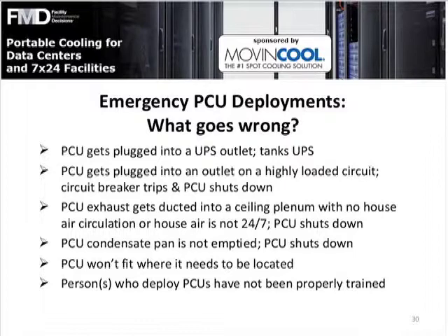Third example, exhaust gets ducted into the ceiling plenum with no house air circulation, or house air is not on 24/7. Remember, all the portable cooling unit does is move heat. It takes heat from the supply air and moves it to the condenser air. If this condenser heat is put into a closed box for long enough, most likely it's going to come back into the room that's being cooled. Temperatures rise in the room, and at some point, something will fail.